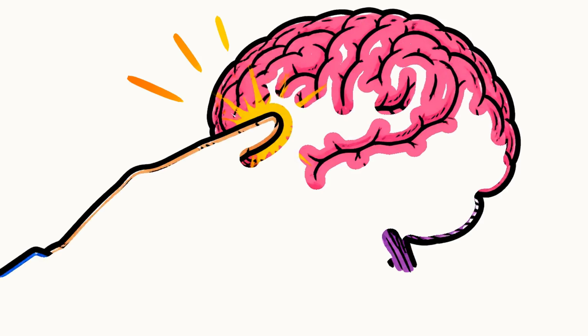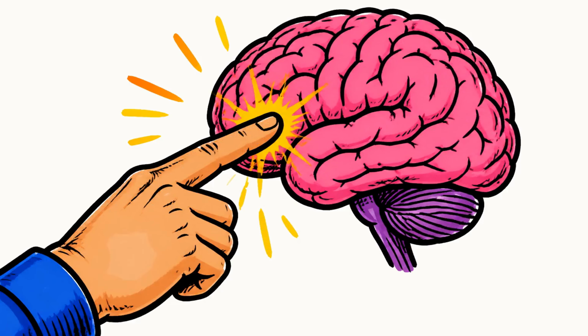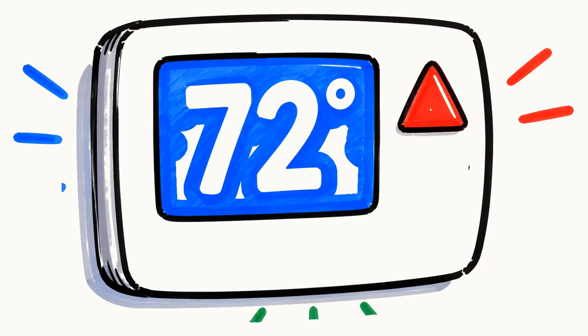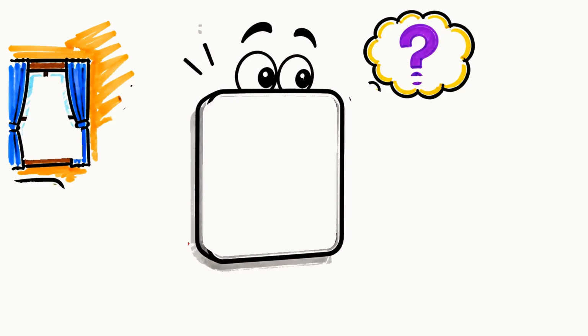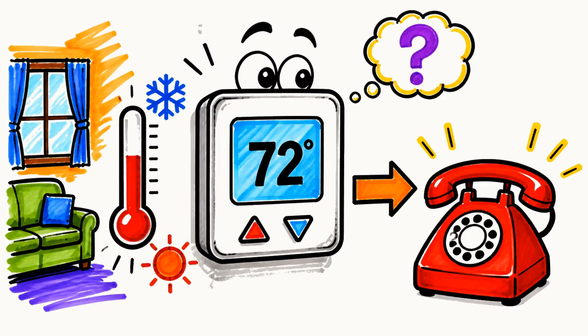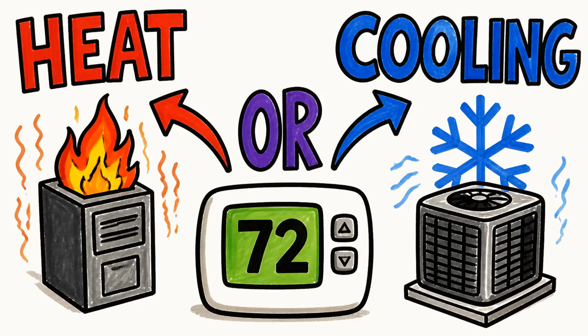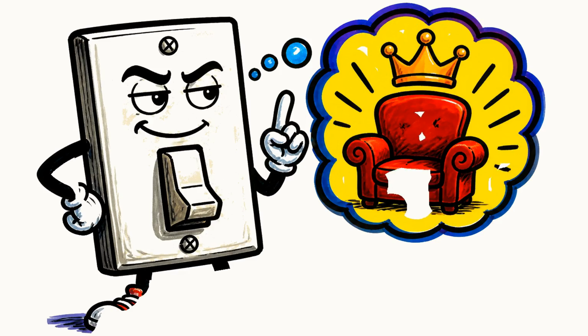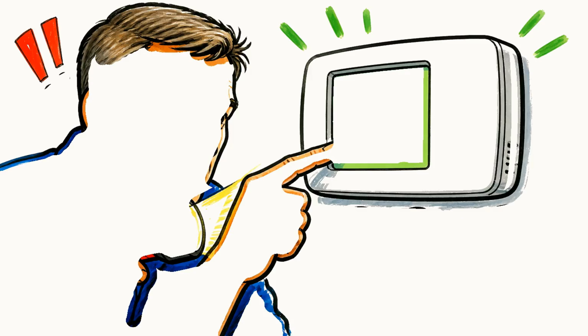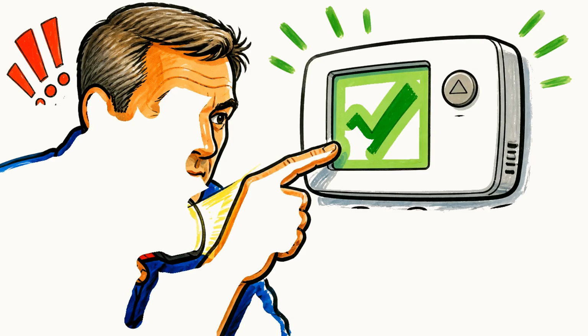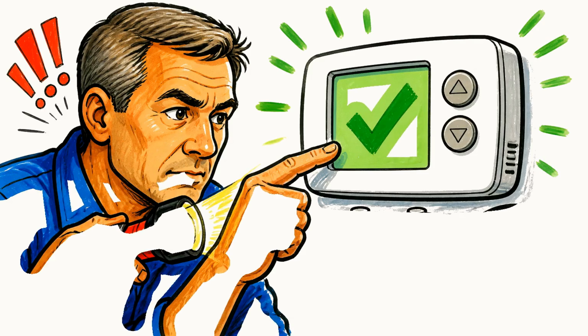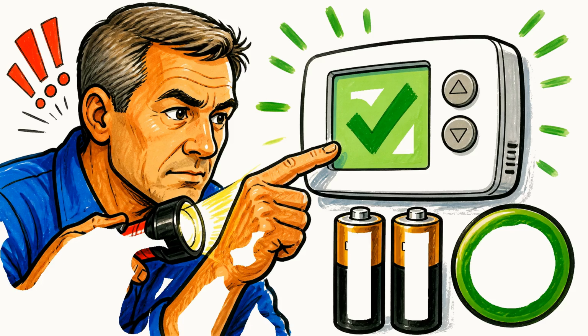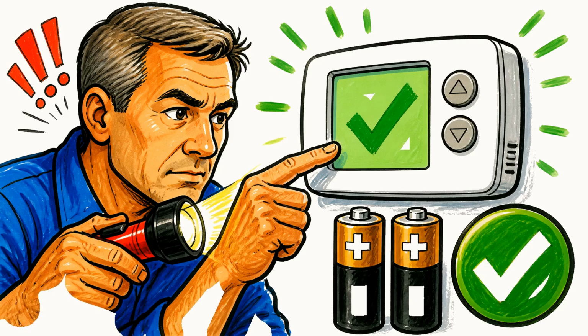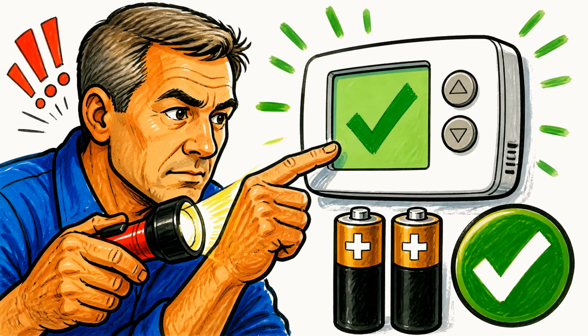Begin with the brain, because it is the part you actually touch. The thermostat on your wall does one job. It watches the room temperature and decides when to call for heat or for cooling. That is really all it does, a switch with an opinion. So when someone tells me their whole system is dead and nothing comes on at all, the very first thing I check is whether the thermostat has power and live batteries, because a surprising number of total blackouts come down to dead batteries and nothing more.